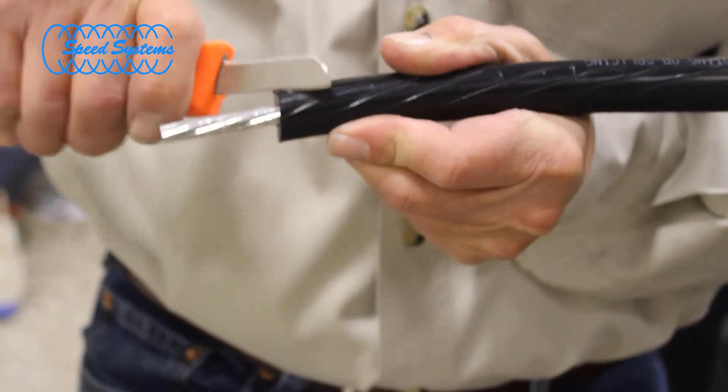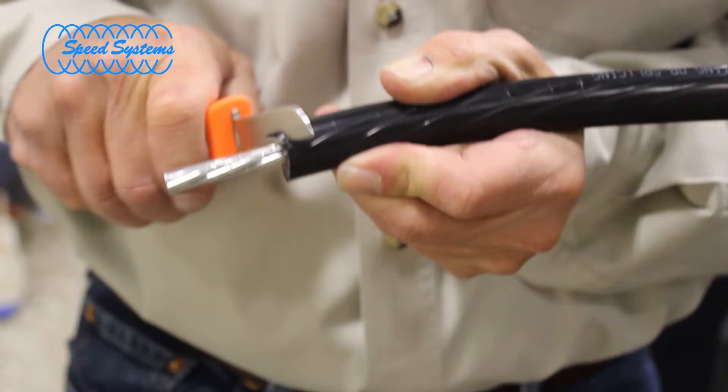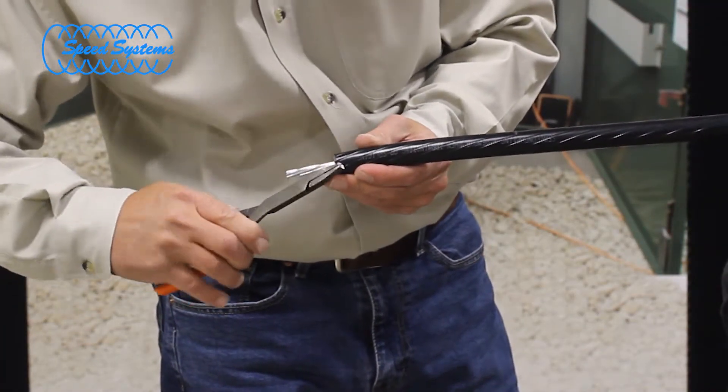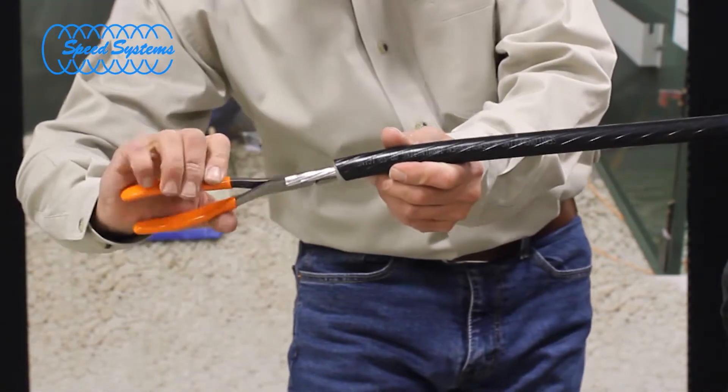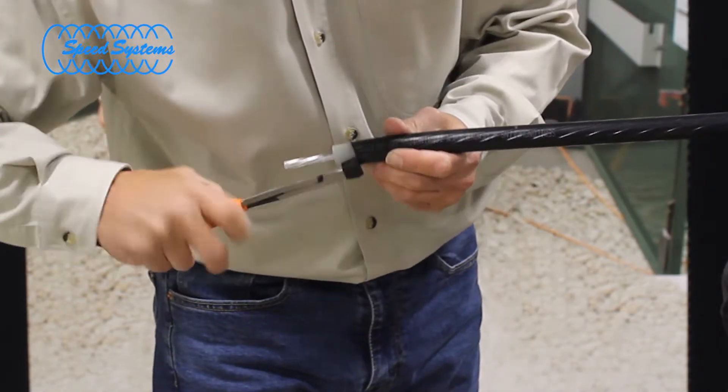Use a knife such as the Speed Systems SC11 edge wedge to lift the edge of the SEMICON so you can grab it with pliers such as the Speed Systems SC13 SEMICON roller grip. Use the SEMICON roller grip to roll the SEMICON from the insulation until you reach the square cut.